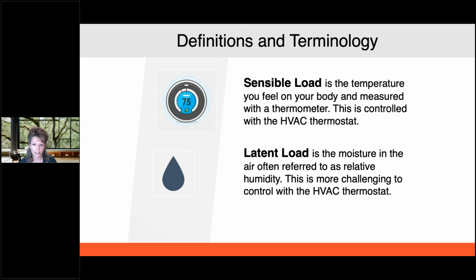So sensible load is the temperature that we feel that is often controlled by the thermostat, and the latent load is the moisture in the air, which is referred to as relative humidity. And this can be much more challenging to control with the thermostat than it used to be in the past. And we're going to dive into how our homes and our equipment's changing and affecting that.